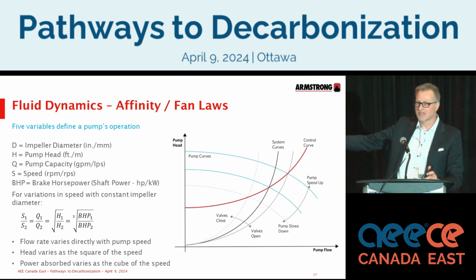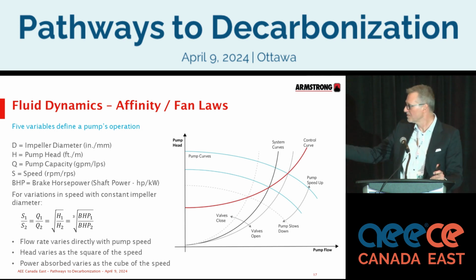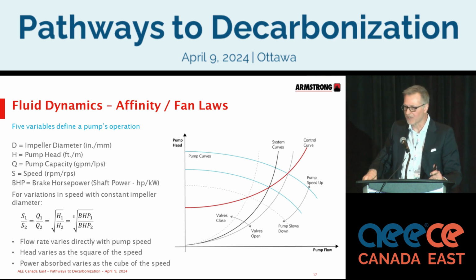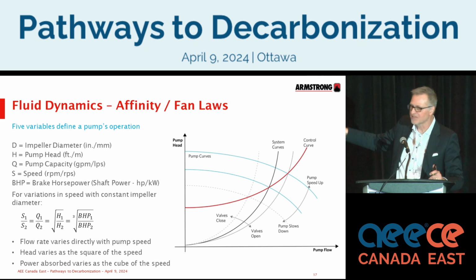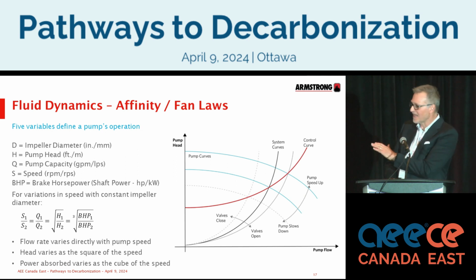So if you drop the speed of a rotating piece of equipment, the energy saved is the cube of the speed ratio. ASHRAE 90.1 stipulation on how to lay out your chilled water loop basically wants you to drop your energy consumption by 70% at 50% load. So understanding that. But the other key here is understanding how rotating equipment, pumps, work in variable flow and what the control curve is. That's one of the key fundamentals. So understanding the control curve and the affinity laws.